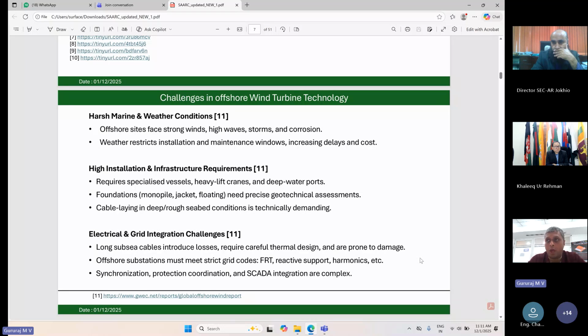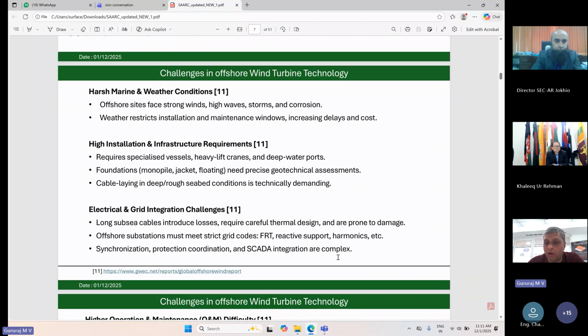Then, let's say you have installed the wind turbine. Ultimately the objective is to convert wind energy into electrical energy, right? So there are issues associated with electrical energy transmission, and eventually bringing the cables to the land as well. Long subsea cables introduce losses, require careful thermal design, and are prone to damage. Offshore substations must meet strict grid codes like fault ride through, reactive power support, harmonics, and these ancillary services. No matter whether we have wind plants onshore or offshore, we are supposed to address these challenges. But offshore becomes even more challenging as we have difficulties reaching the turbines in case of any cable damage. So protection, coordination, synchronization, and SCADA integration could be a complex game.